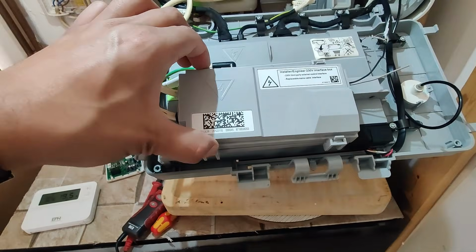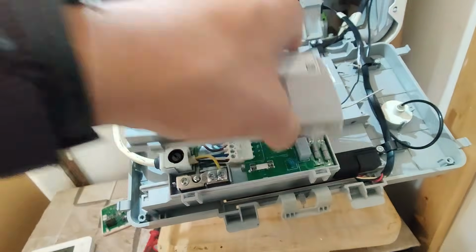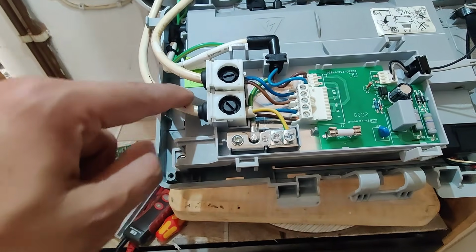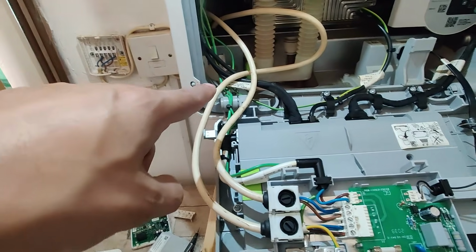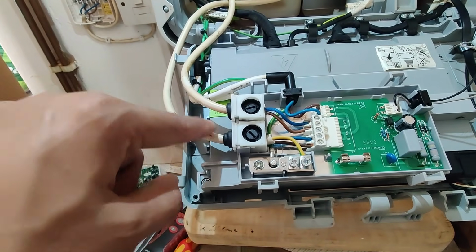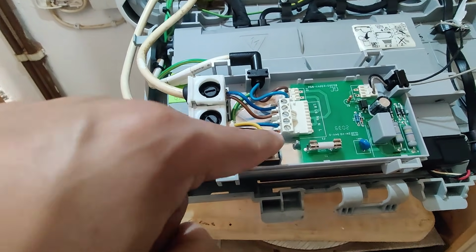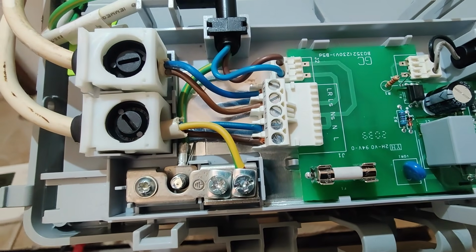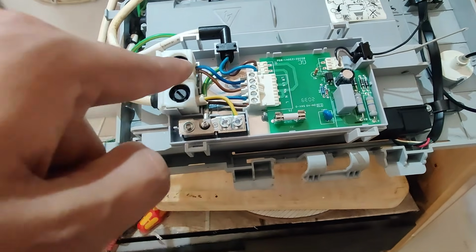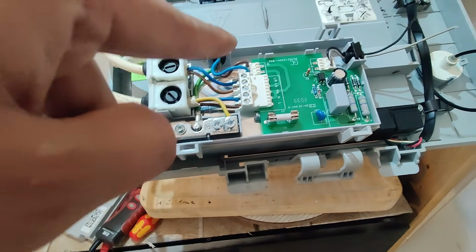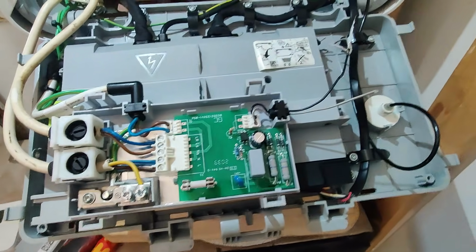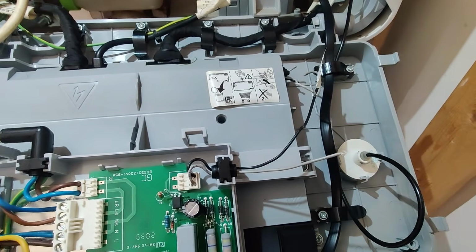With this boiler, let me just isolate it so we can work on it safely. So when you remove this cover, your cables are coming in here. They've not used a 5-core, so they've used 2-3 cores, which is absolutely fine. So they've got live and neutral and earth, and then they have live supply and live return. So that's your loop basically. That's bringing the power and the signal to this small PCB, and then that's transferring it to the actual main PCB there. But look at these cables.